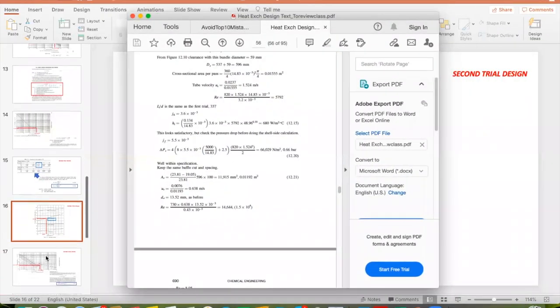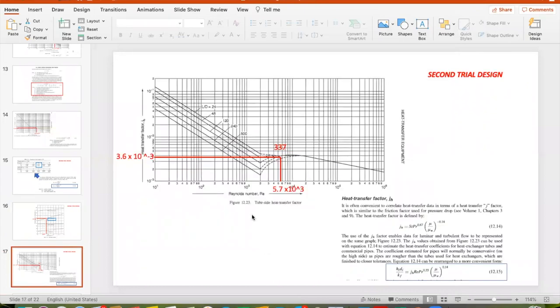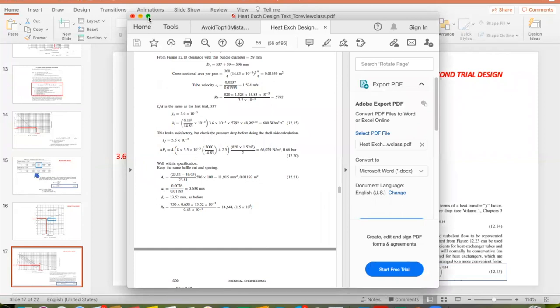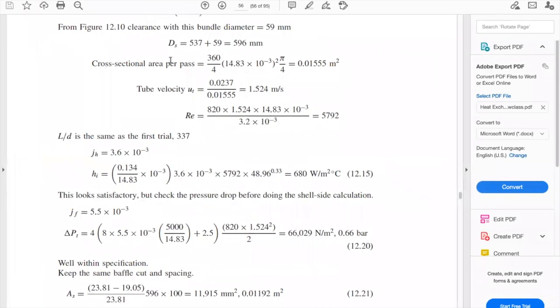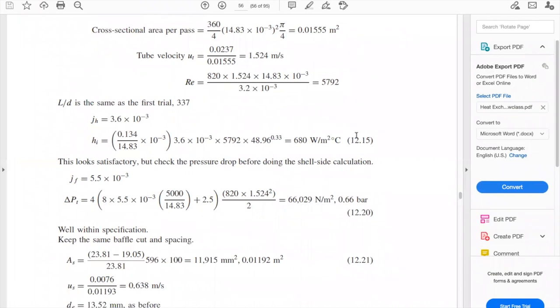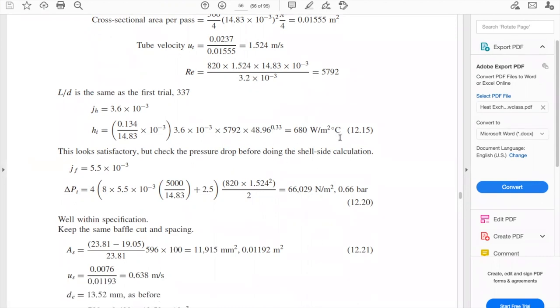In figure 12.23, we have a new Reynolds number with the same L/D, so we go all the way to the left and get a new heat transfer factor of 3.6×10⁻³. Using equation 12.15 again, we have a new H value of 680 W/m²°C. The book says this looks satisfactory, but whatever this number looks like, you need to check the pressure drop — that is a very important thing to do.